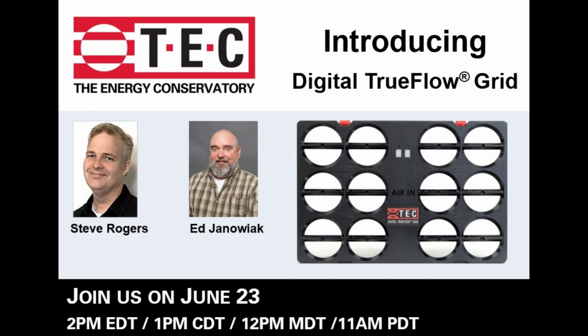With the right airflow. Yeah, I was stoked, because I would have normally gone ahead and cut that return and made it bigger, but not necessarily have to. We've always lived by total external static. If you're like me, we're fast paced in the field, moving like crazy, we rely on the blower chart. That's where we're going with it. Now that we're going to be able to see flow and total external static, and compare the two at the same time, I think our technical game is going to go through the roof.